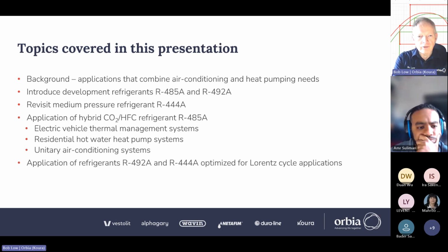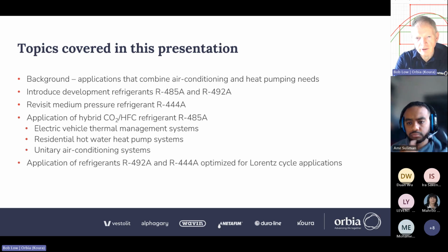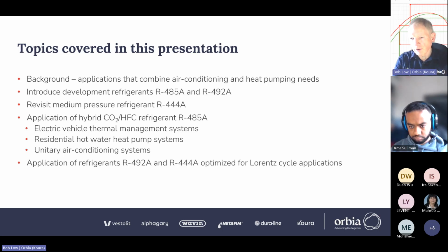So I'm going to be covering the use of R-485A in transcritical technology and CO2 technology, really. And the reason we're covering it in that technology is the blend is 69% CO2. So it's CO2 with some fluorocarbon added to it to alter the performance parameters. And we're testing that actually in electric vehicle thermal management systems, residential heat pump water systems, unitary AC systems, and also commercial refrigeration systems. And I'll come on to that in the presentation. The other two refrigerants, I'm focusing on their use in Lorentz cycles. So this is where the source and sink fluids have temperature changes which are non-negligible. And this allows exploitation of the extra degree of freedom that a blend gives you in terms of the variation of temperature through the condensation or evaporation processes.